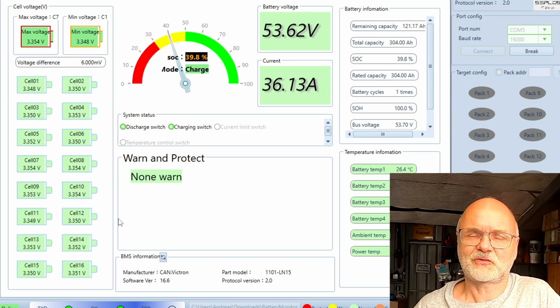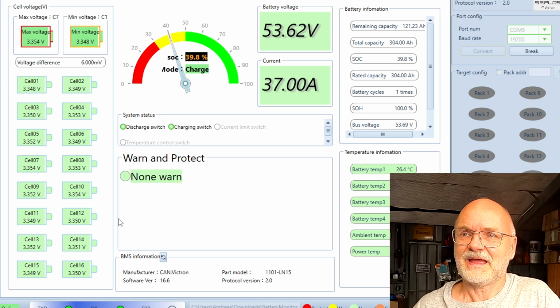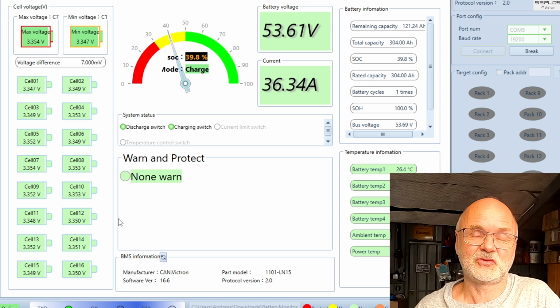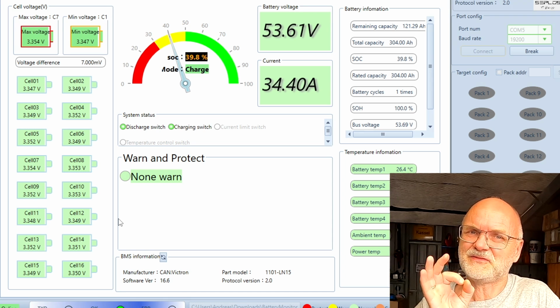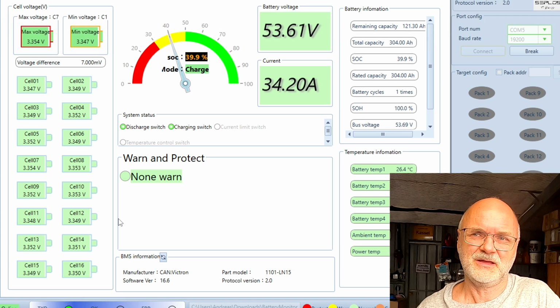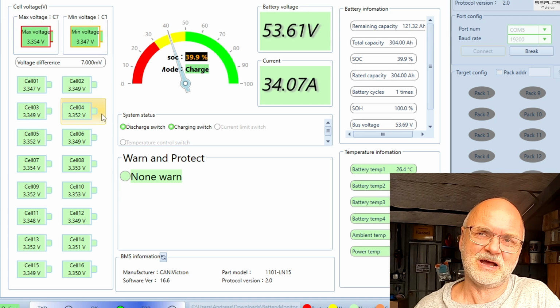So even though I have torqued all the flexible bus bars down onto the battery terminals with 7 Newton meters, I have not double checked it as I would usually do. And this was a bit on purpose. I said, well, if I have missed one of the connectors over there, it will show up during charging.